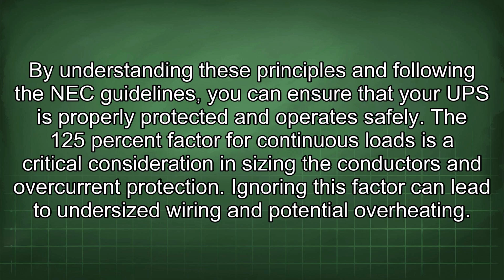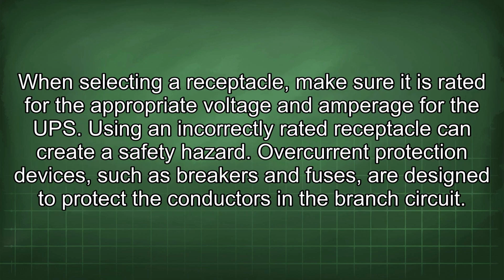operates safely. The 125% factor for continuous loads is a critical consideration in sizing the conductors and overcurrent protection. Ignoring this factor can lead to undersized wiring and potential overheating. When selecting a receptacle, make sure it is rated for the appropriate voltage and amperage for the UPS. Using an incorrectly rated receptacle can create a safety hazard.